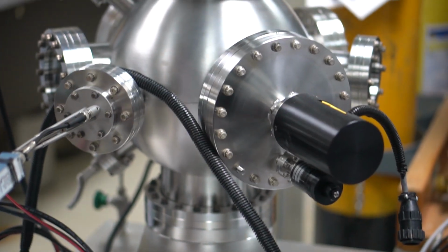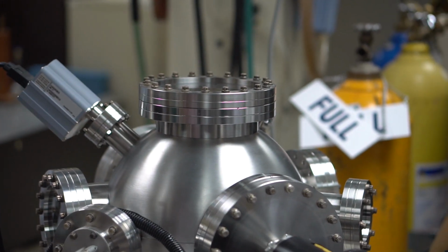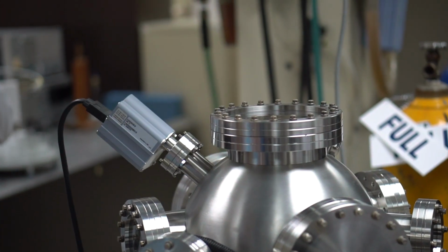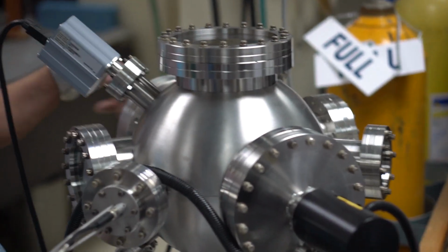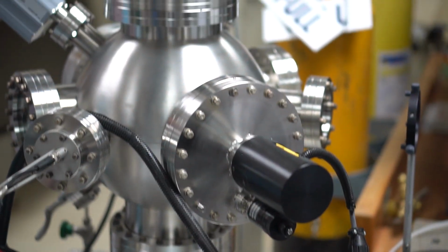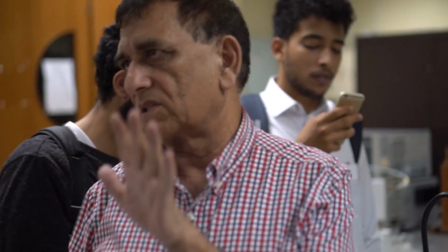The beam, which is Gaussian, you can say, has its maximum intensity in the middle. So the beam comes through this, we focus it, and we put the target here. And the target is rotating all the time. At one time we can load 6 targets. For example, we can put zinc, titanium, copper, silver, all of these, 6 of them, and they are rotating continuously. And on this side, we have the substrate on which we want to make the film. It is roughly 2 inches away, okay.